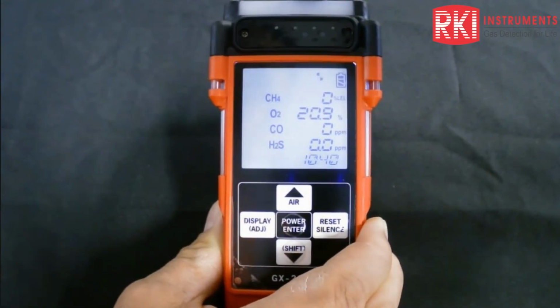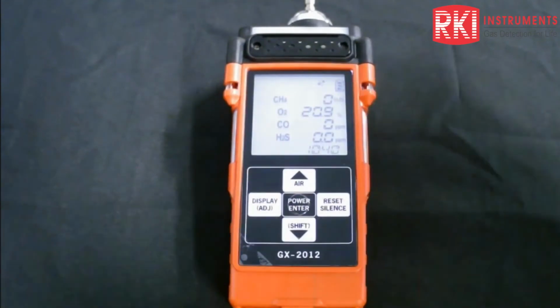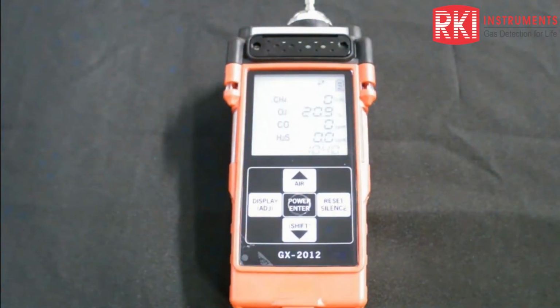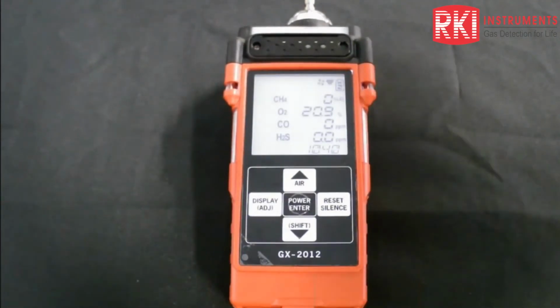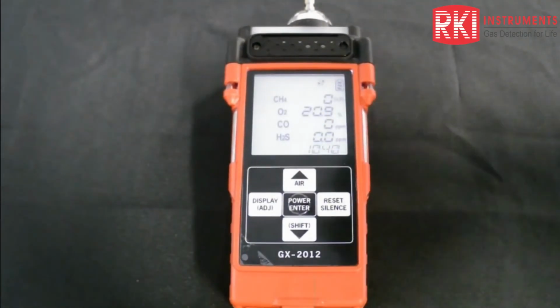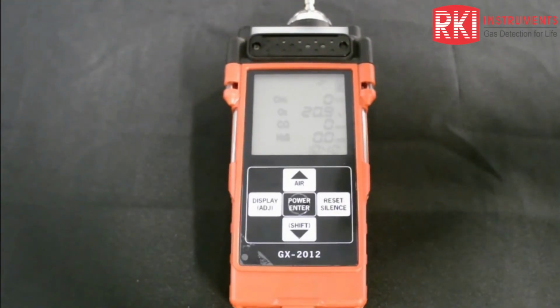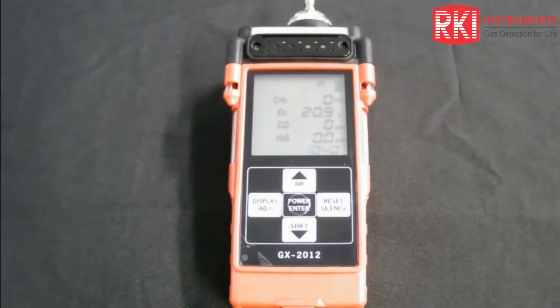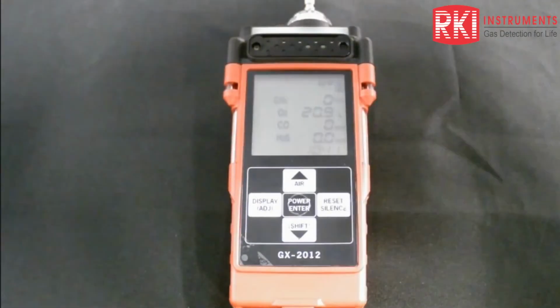I was going to say what we did, guys, is, for instance, if we walked up to a pipe that was full of percent by volume gas, you'll see how fast it will react if you put the nozzle of the instrument close to it. And it's nice to see that because normally it's not going to happen that way. You will be moving towards an area or location normally in an occupational health and safety mode. We're worried about the person. And you'll see that unit climb up through the LEL slowly, like you're walking into a cloud of gas. And then as you're made aware of it, you're going to be looking for a higher concentration. And that's from the percent by volume, or that's the application that you're using it in.